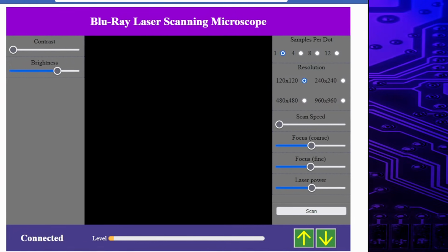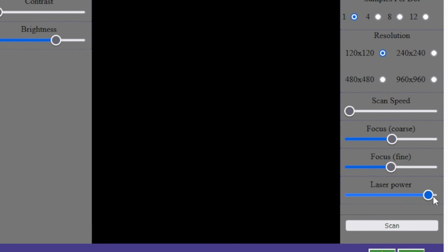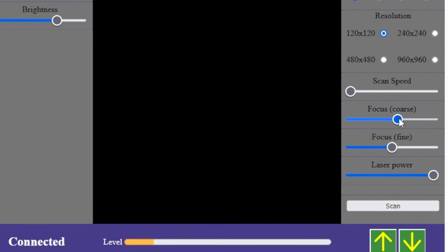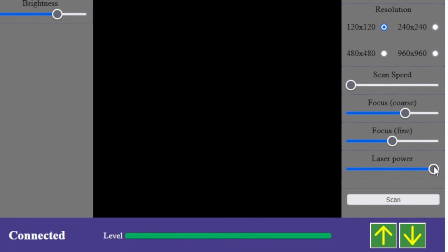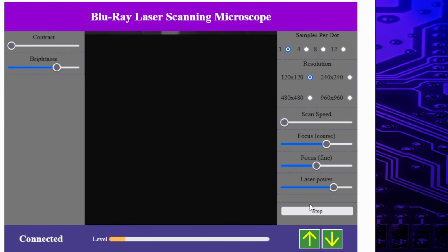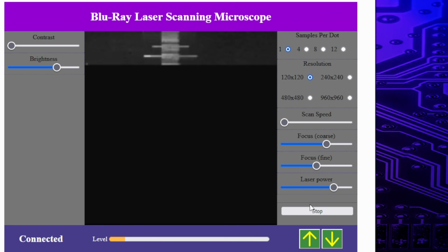Back to the website. With the laser at maximum power, I move the focus slider until the indicator at the bottom reaches its maximum. Then I take the laser power back a bit and search for a maximum with the fine focus control. Doing so brings the sample exactly into the focus of the laser. There we are. Then I click the scan button to start the process. There comes a grey horizontal bar and some vertical lines. Now the calibration pattern is formed.